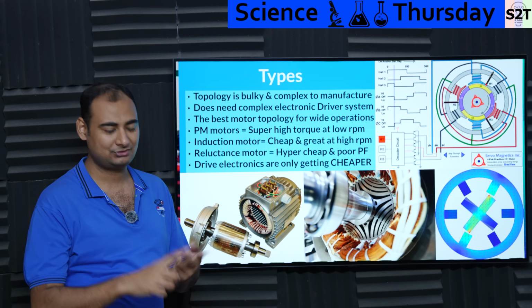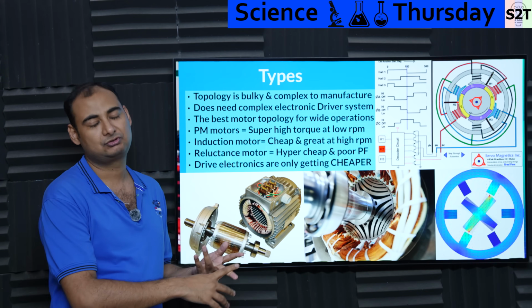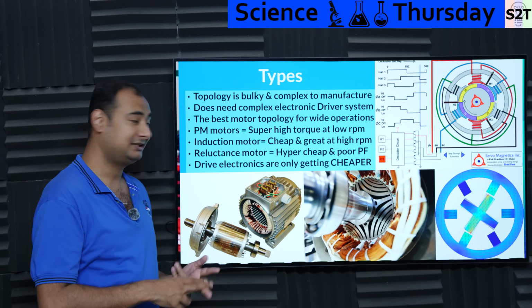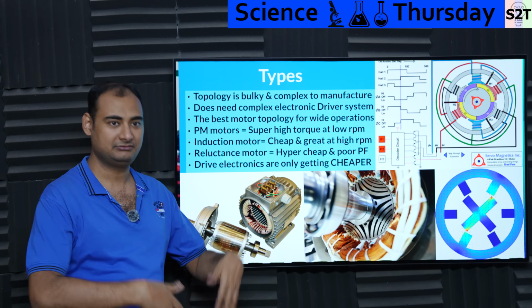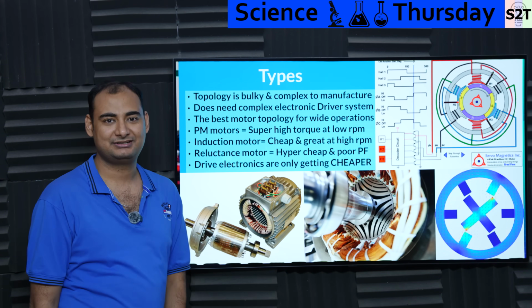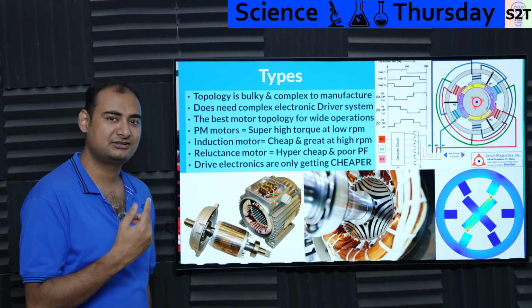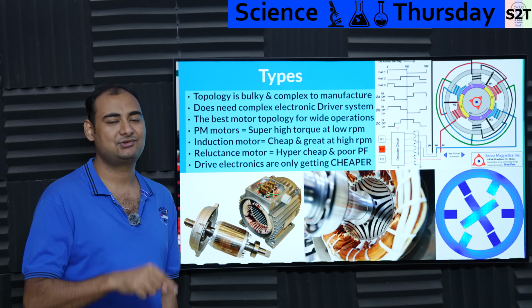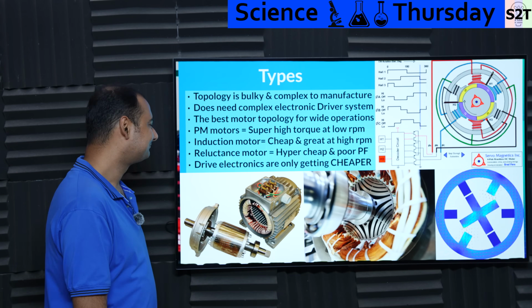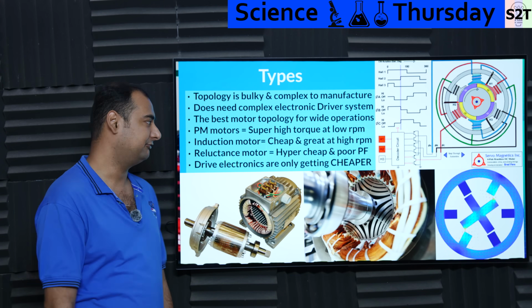So that sort of control is available: you can allow it to coast, stroll downhill without any issue, or if you want to retard the speed, like on a truck, increase the rotor current. Everybody can control the stator, but only this design allows you to control the rotor. That's why we pay attention to this system.